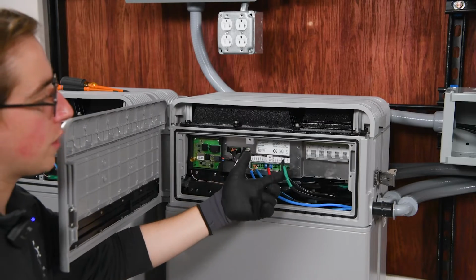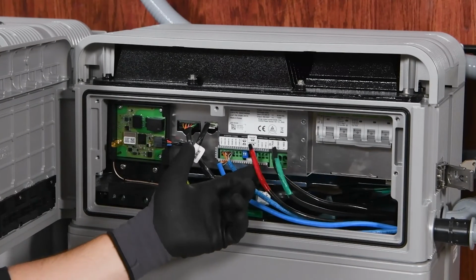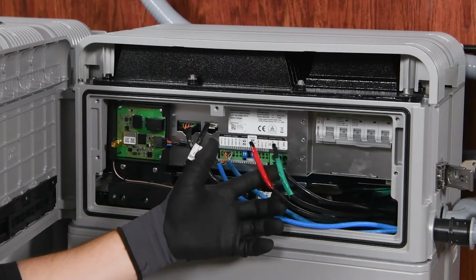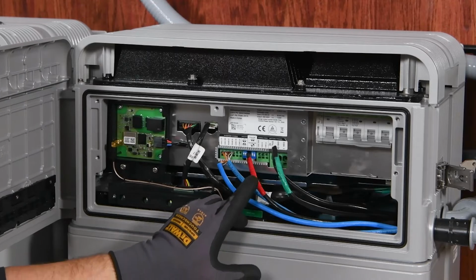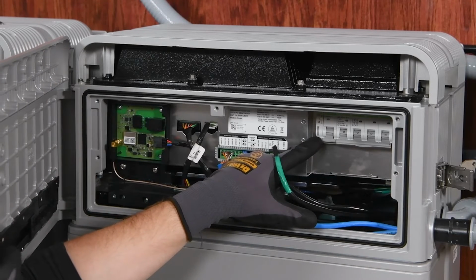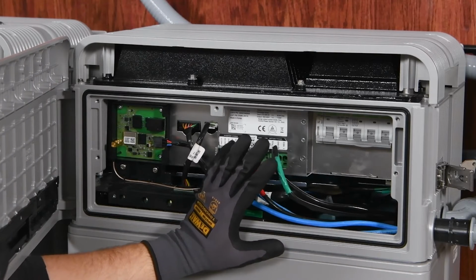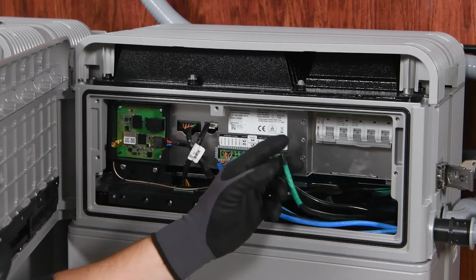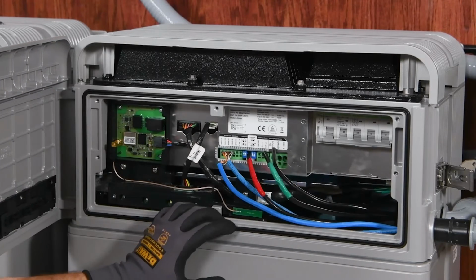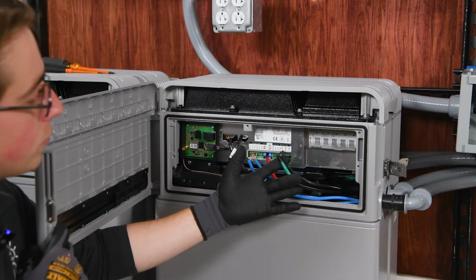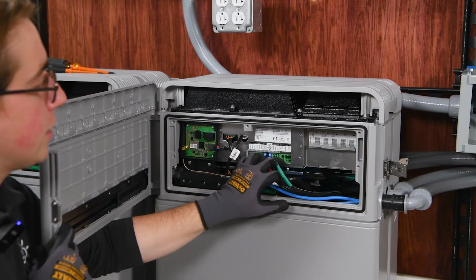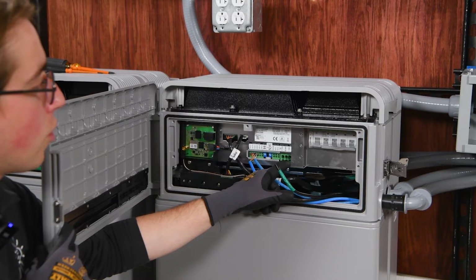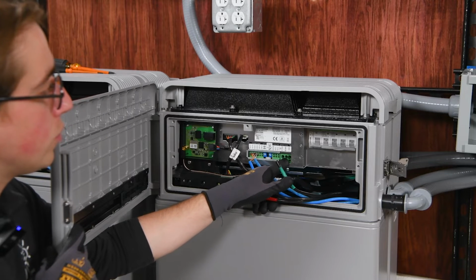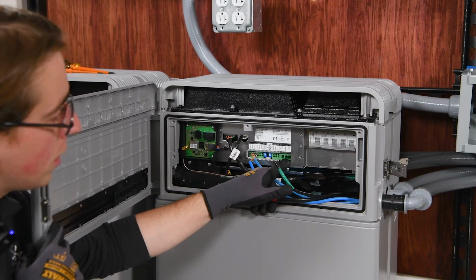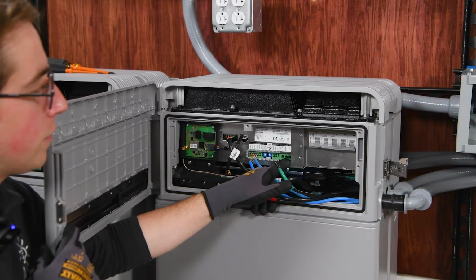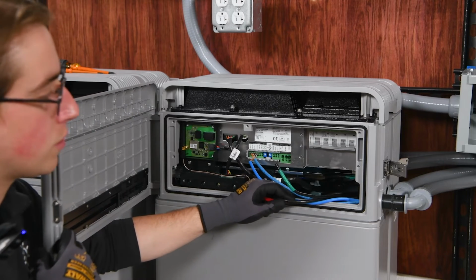We are now at the step of connecting our battery conductors, our positive, negative, and ground, to the battery itself. Remember to make sure that the breakers are in the open or off position. We don't want to connect any live conductors, and we don't want to turn on the system just yet. Again, we're going to use ferrules for our connections, and similar to the connection with Growatt, we're going to push into the connection ports here, and the jaws or the teeth are going to bite into the ferrules, and we'll give them a light tug to make sure that they don't go anywhere.